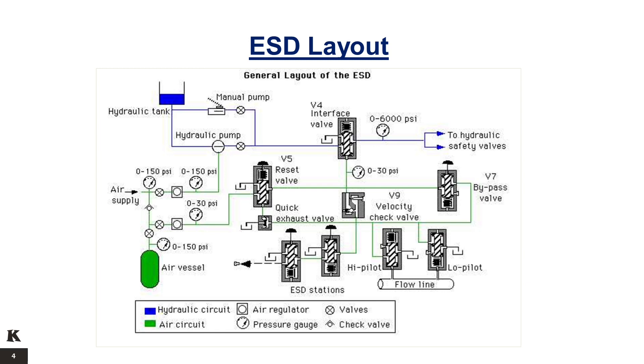If the low pilot senses the flowline pressure is above the preset value, fixed by the adjustable spring force, air supply pressure is retained between the low pilot and the interface valve in the console. Hydraulic pressure from the pump is allowed to go to the hydraulic actuator, keeping the shutdown valve open. When the flowline pressure falls below the preset spring value, air is bled off at the low pilot, the interface valve vents the hydraulic pressure from the actuator, and the shutdown valve closes.